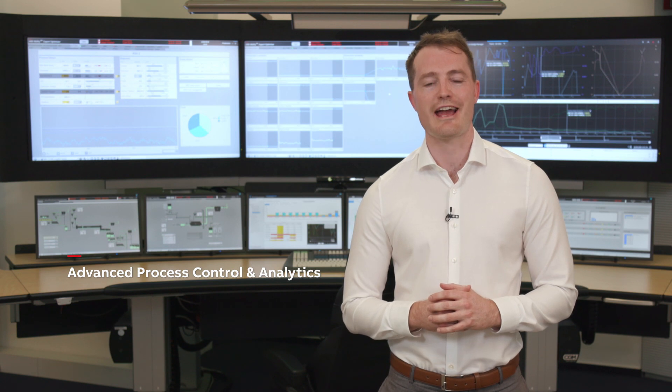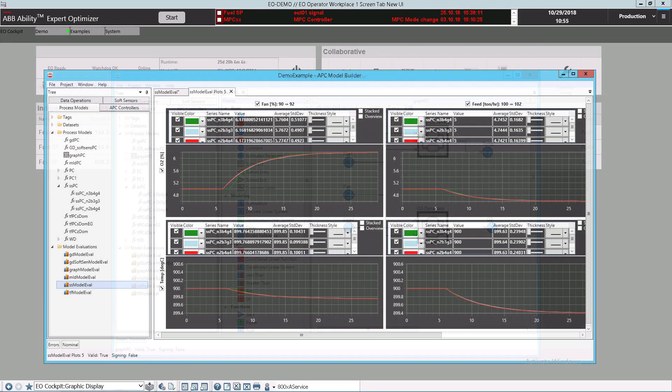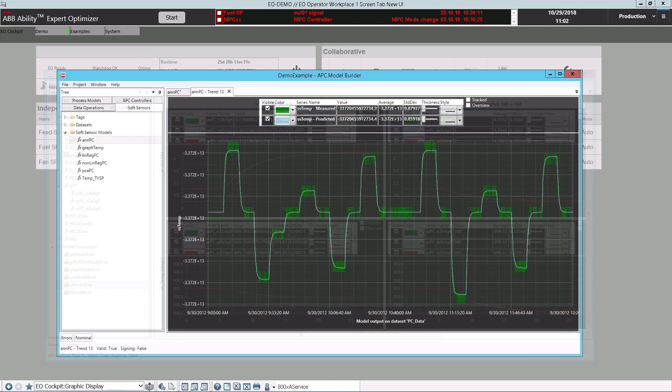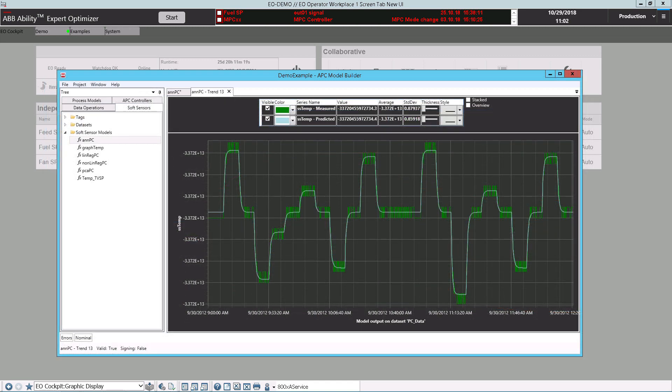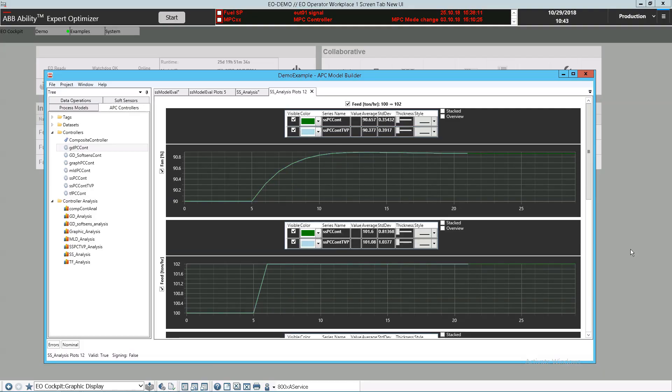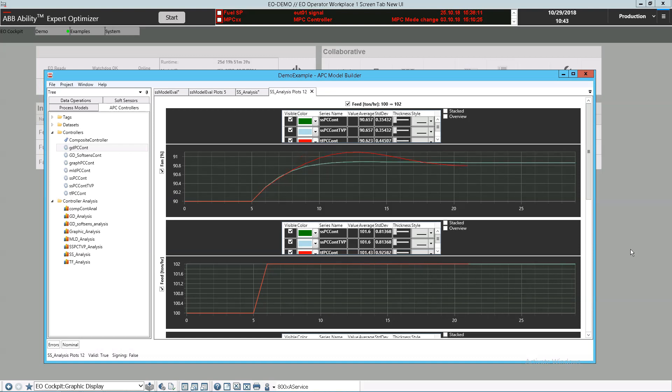The major tools and technologies used in Expert Optimizer are housed in ABB's Advanced Process Control Analytics Model Builder, where the means for developing first principle, fuzzy logic, model predictive control, and soft sensor type models are all available in one application, as are simulations for different controller tunings. This reduces time spent on site commissioning.